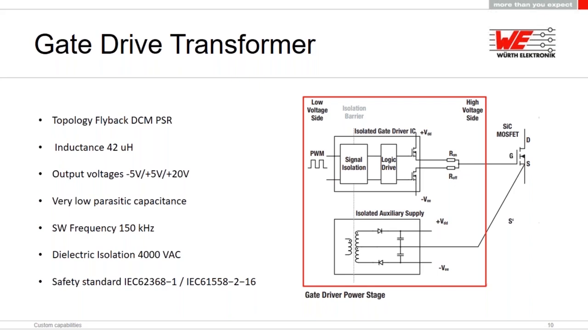It provides the positive and negative output rail for a faster turn-off transition. In addition to the two windings that the gate drive transformer provides for the positive and negative voltages to drive the SiC switcher, the transformer assures galvanic isolation between the high and low voltage side. This is a requirement not only to meet the safety standard, but also to reduce electrical noise, as well as to improve the EMI and the gate drive control robustness.